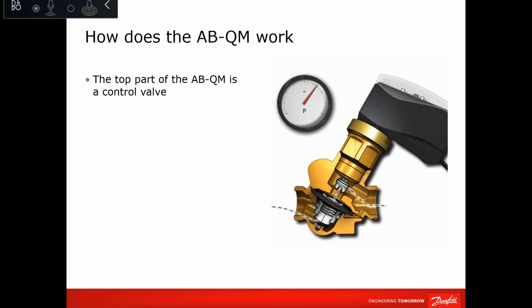It is good for, you can measure the flow using the KV methodology, and extra, you can measure available pressure across the whole valve and the available pressure across the DP part. What is the valve resisting, to what pressure from the system? It is good for troubleshooting. But for the flow measurement, all the sizes you can measure. On the small sizes, you have 2 test ports due to space. We don't have enough space for that. And these 2 test ports can be used only to measure the flow with the KV methodology. So on the bigger one, we have space, we put 3. On the small one, we don't have, we put 2. But we made sure that regardless of the size, at least 2 of the test ports will be measuring the control part of the valve differential pressure, which is used for troubleshooting and flow measurement.